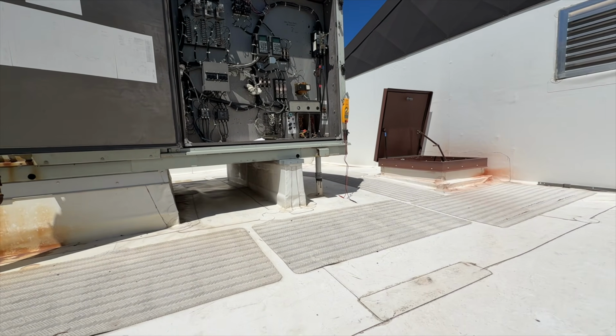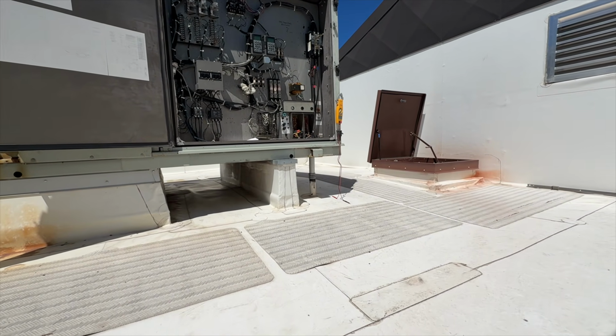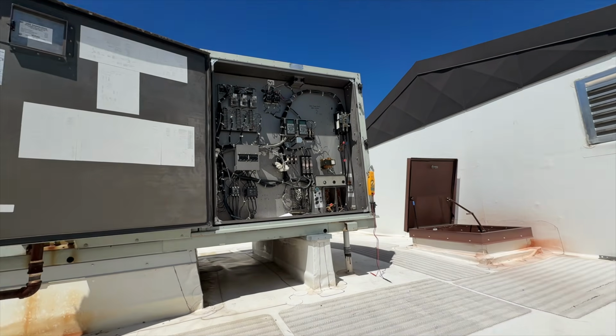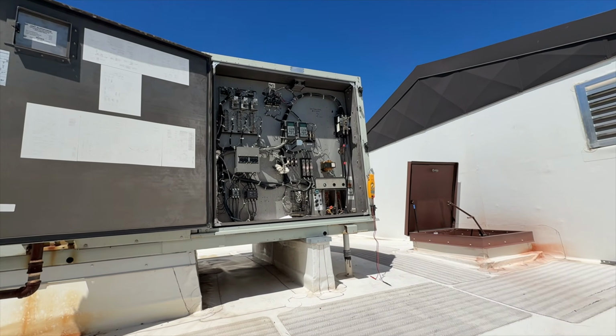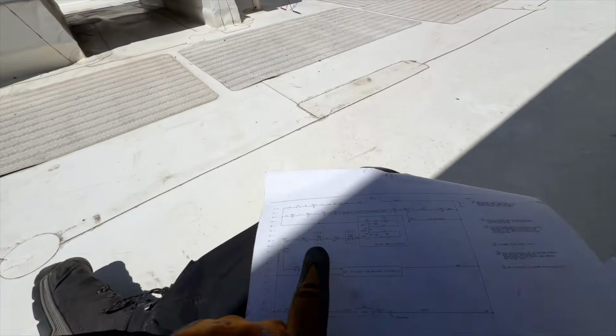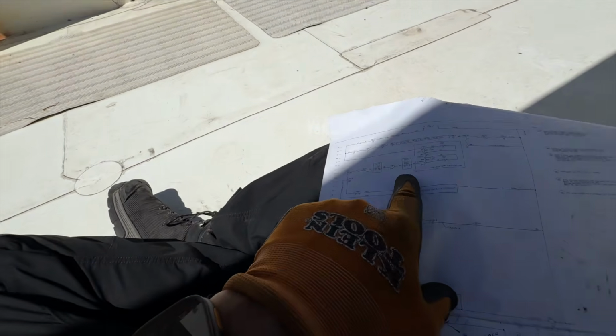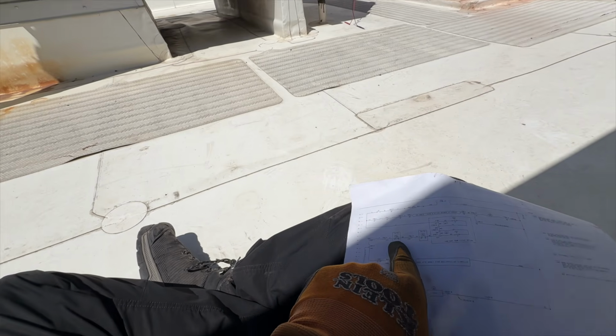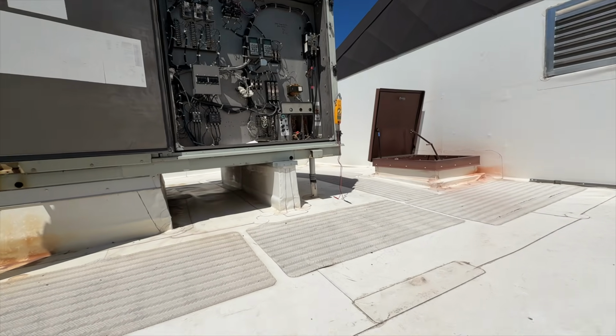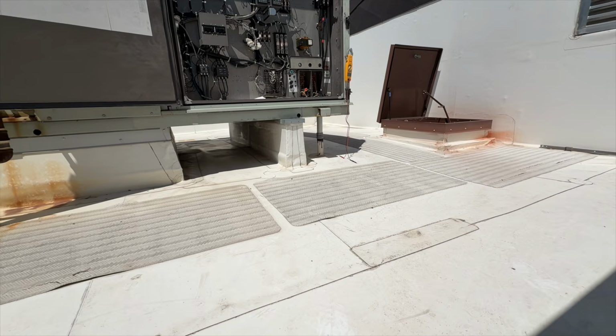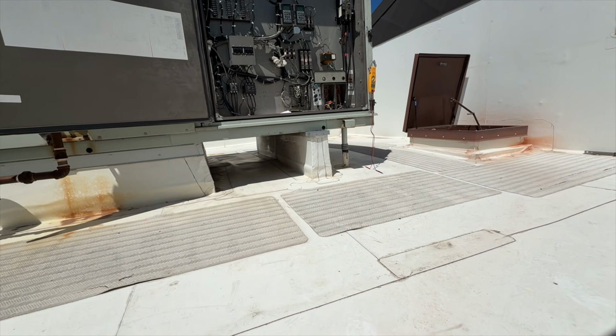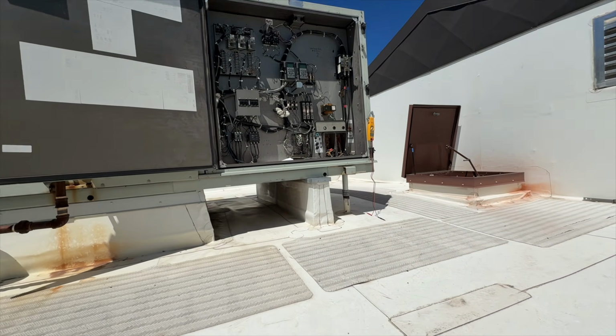I suspect that transformer is controlling the control system, okay? Only one of my VFD monitors is on. So I'm thinking one of these, hopefully if they're the same, the one on the left that's powered off could be killing the high voltage to that transformer, which is killing the control system. That's what I think it is. So I need to find that VFD and locate it.